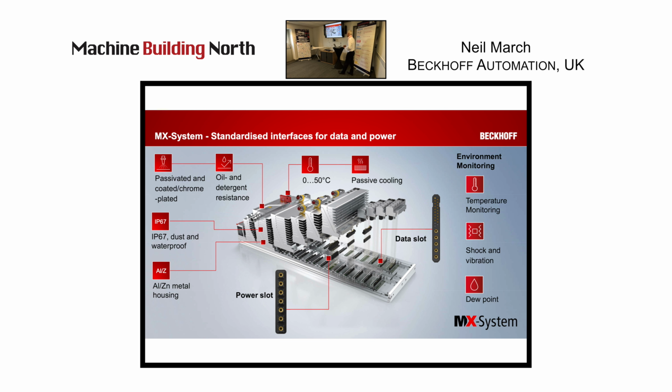The housing, aluminium, zinc, IP67, it's passivated, protected, and it can work up to 0 to 50 degrees. Passive cooling, so there's no forced cooling, but also contained within there is environmental monitoring. This monitors the temperature of the unit itself, as well as shock, vibration and dew point.